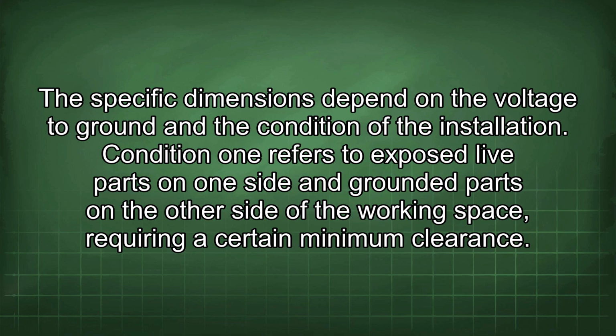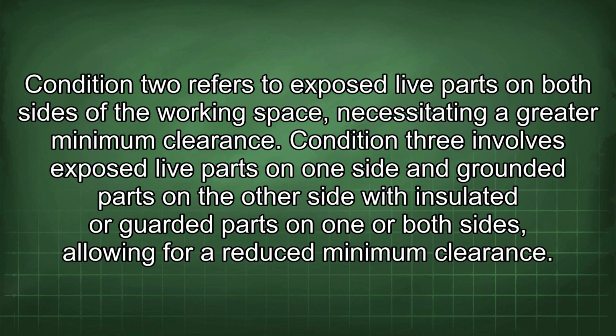Condition 1 refers to exposed live parts on one side and grounded parts on the other side of the working space, requiring a certain minimum clearance. Condition 2 refers to exposed live parts on both sides of the working space, necessitating a greater minimum clearance. Condition 3 involves exposed live parts on one side and grounded parts on the other side with insulated or guarded parts on one or both sides, allowing for reduced minimum clearance.